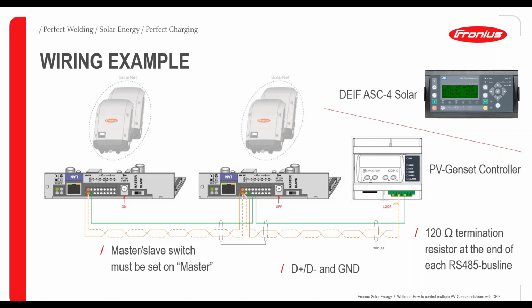So when we look at a bigger system, we tend to cluster, let's say 5 to 10 inverters into a solar net ring. So a Fronius communication between the inverters, and per Fronius inverter cluster, we have then one data manager, and these data managers are connected via Modbus in this case. By doing this, we are having less risk if a solar net ring is failing, or if there is any disturbance, that not the whole PV system is shut down, but only a portion of this system.